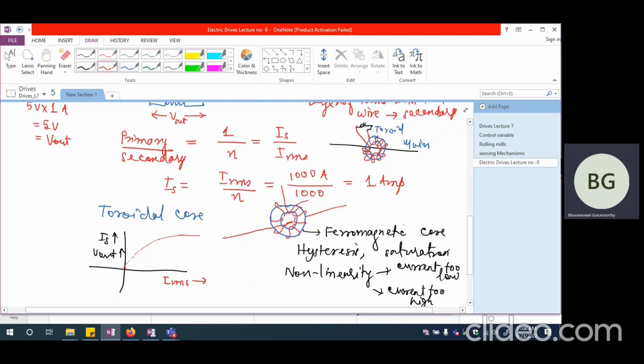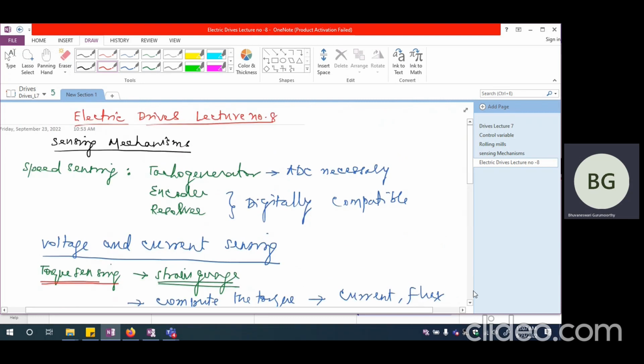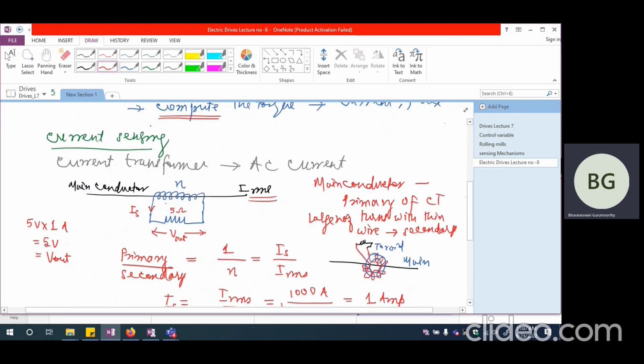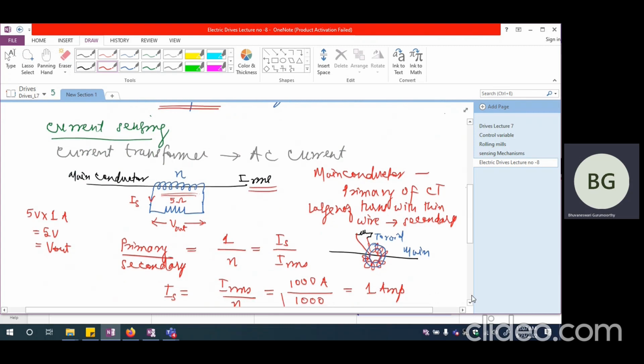So I will not have a linear relationship between the input current and the secondary current or output voltage at very low current values as well as very high current values. So the range has to be specified very clearly for how long the current transformer can work. This is one problem that could creep up with the current transformer. Otherwise, the current transformer is a very simple arrangement because it's just a transformer in action, and transformers are always characterized by very high efficiency. So you will hardly see any losses. This is one of the major advantages of using a current transformer.